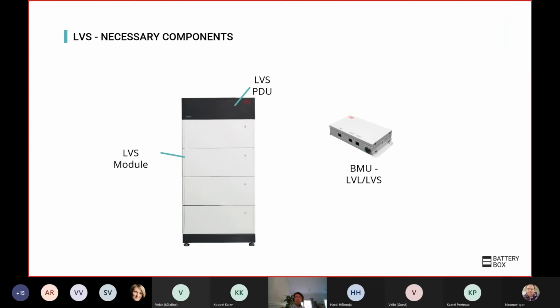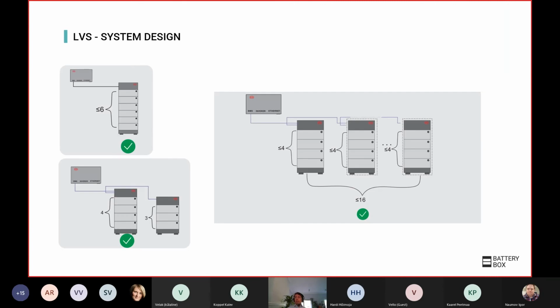Each of these towers will include the actual LVS modules, and a PDU and base will be on top and bottom of the unit. And then, same as with the LVL, you'll have the BMU, which will be the communication interface with the inverter. So just one per system. In terms of the restrictions of these towers, I mentioned before you can have 4 modules per tower, but there is one exception. If you only have one tower, that one tower can have up to 6 modules. But if you have more than 6 modules, they will need to be in several towers. As these are connected in parallel, you don't need to have the same amount of modules per tower. So you can have 4 in one and 3 in another.